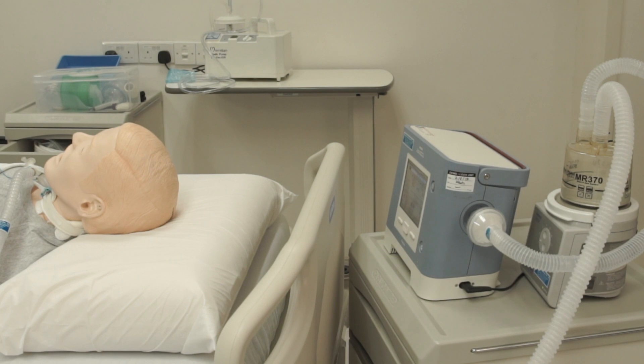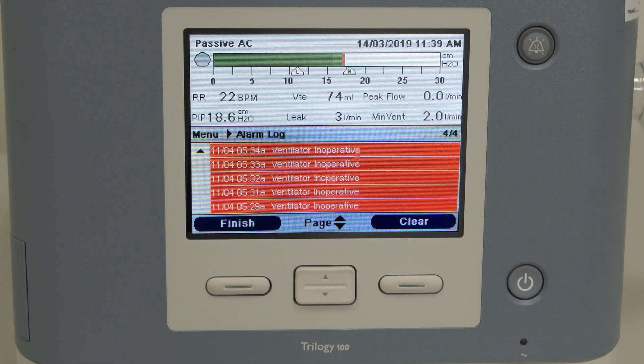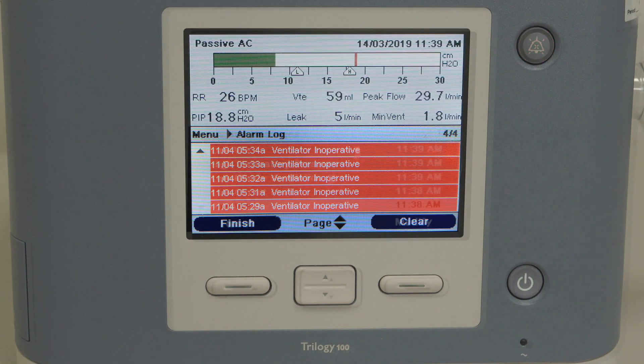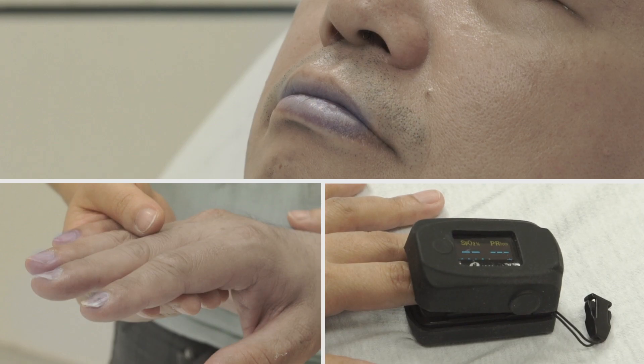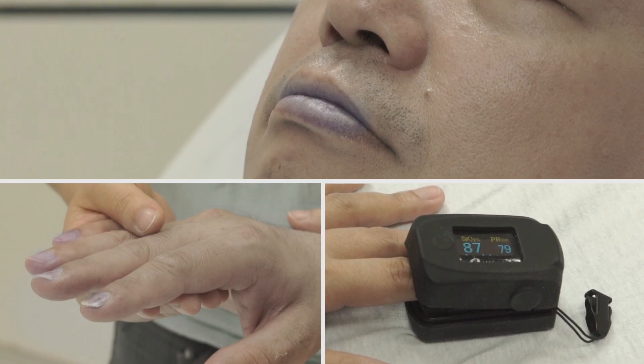You may suspect a machine failure if you notice the following signs: a continuous ventilator alarm after troubleshooting for all possible causes, a blackout screen when the machine is not in sleep mode, no chest rise or no airflow from the ventilator, or the patient's face and fingernails turning blue or a low SpO2.